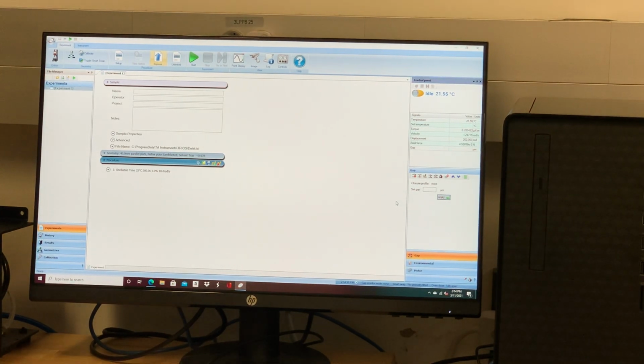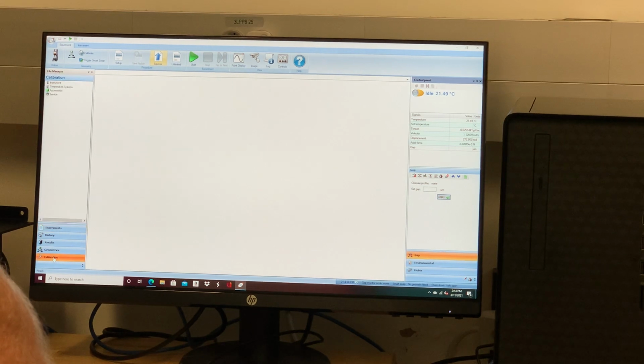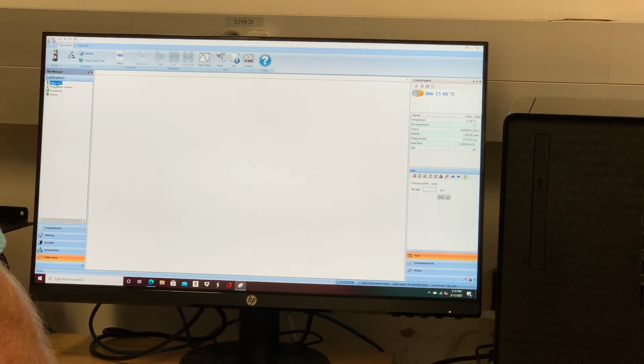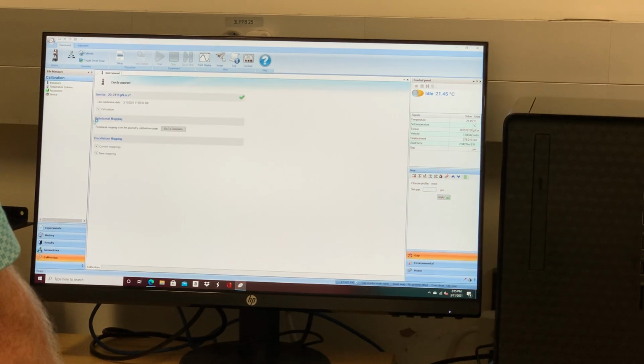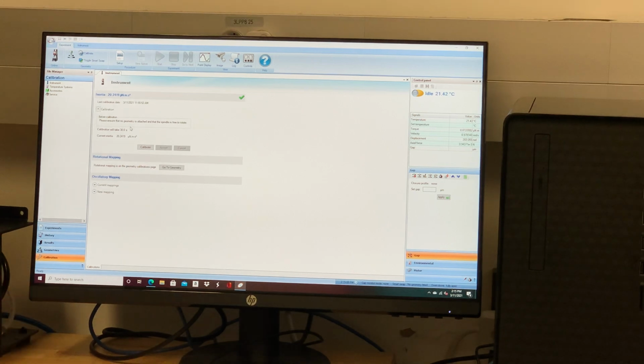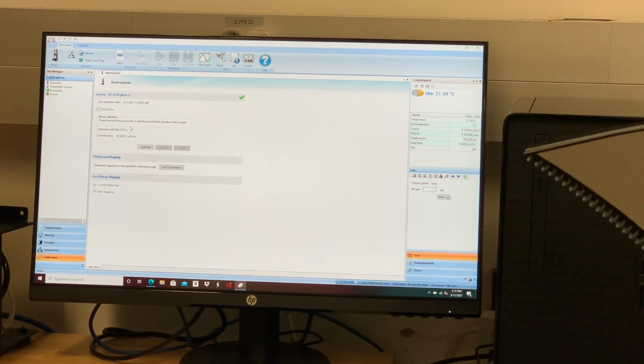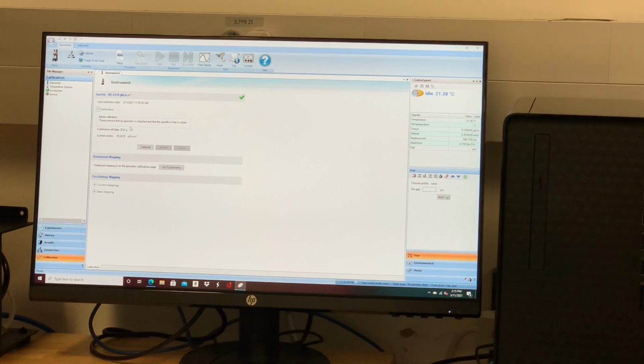Okay, so the first thing I'm going to go over are the calibrations you need to do. The first calibration is under the calibration ribbon here, the instrument calibration, instrument inertia calibration. Because this is a CNT rheometer, everything's up here, you need to correct for inertia. Okay? Very easy.